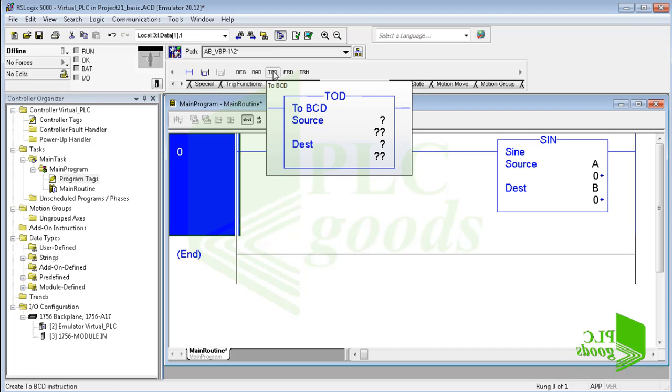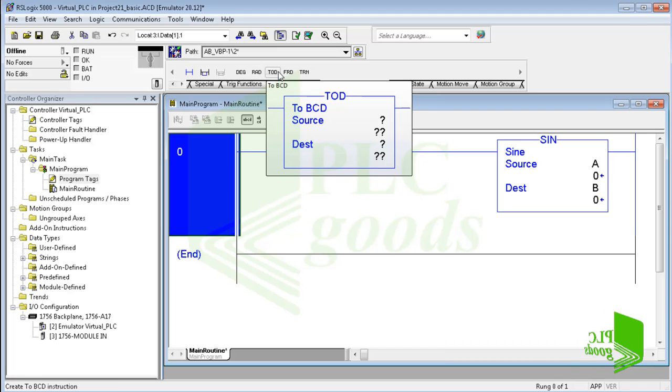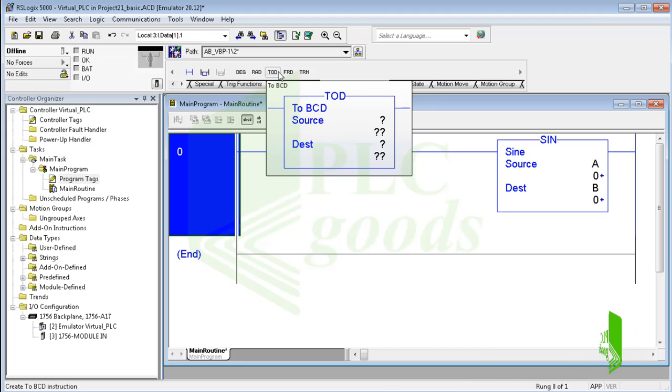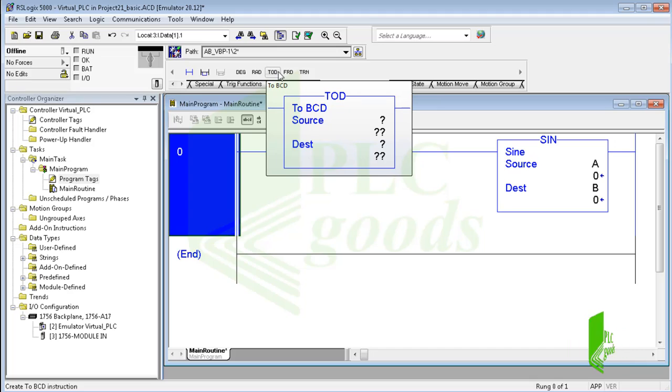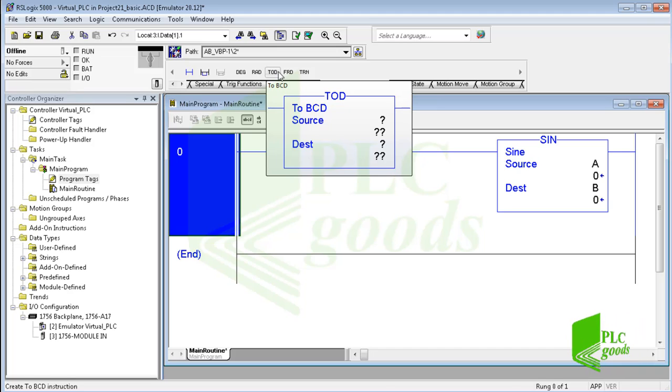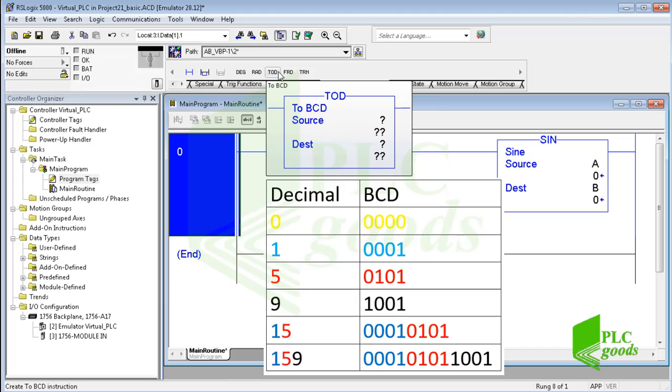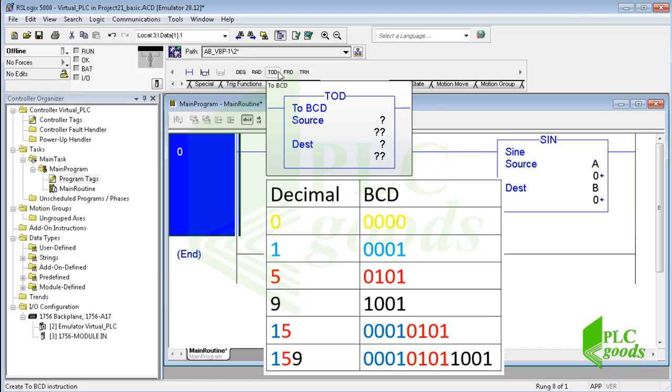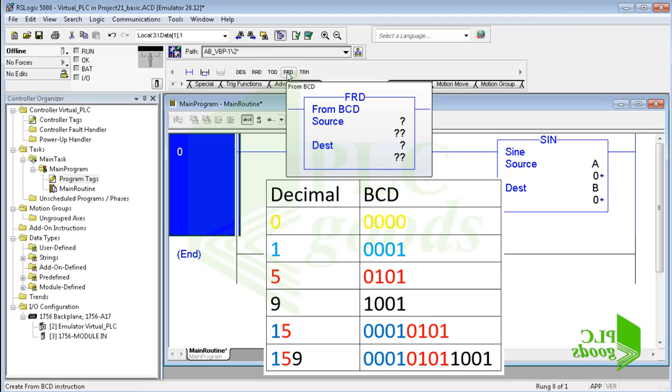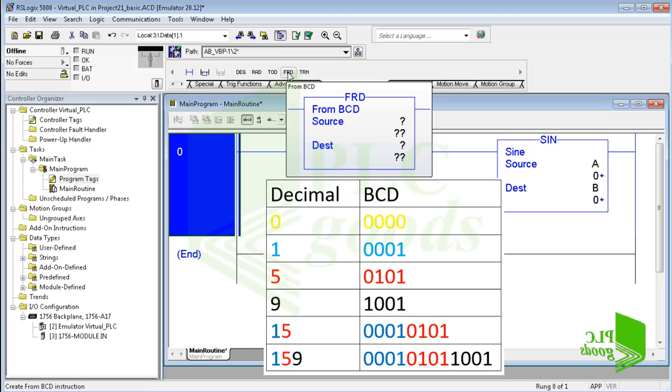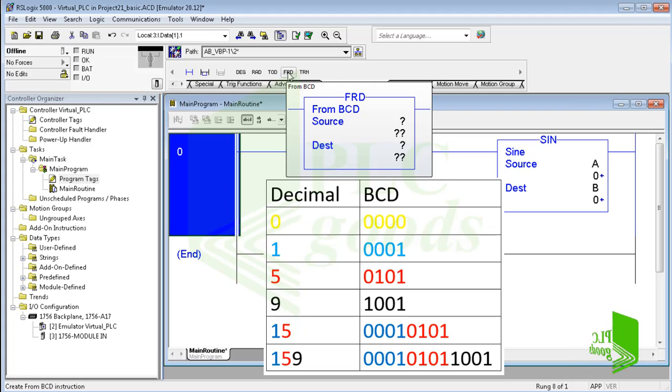The TOD instruction converts a decimal value to its BCD value. BCD is the binary coded decimal number system that expresses individual decimal digits 0 to 9 in a 4-bit binary notation. This table shows some examples of decimal numbers and their equivalent BCD value. Note that the FRD instruction works inversely, it converts a BCD value to its decimal value.